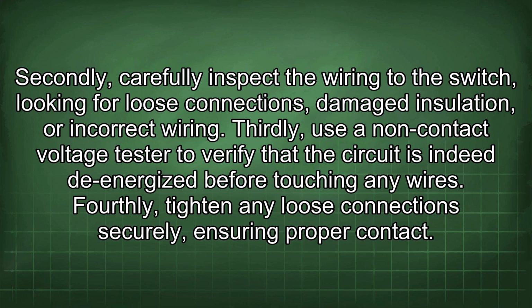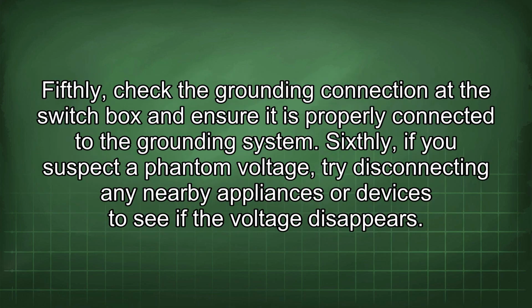Thirdly, use a non-contact voltage tester to verify that the circuit is indeed de-energized before touching any wires. Fourthly, tighten any loose connections securely, ensuring proper contact. Fifthly, check the grounding connection at the switch box and ensure it is properly connected to the grounding system. Sixthly, if you suspect a phantom voltage, try disconnecting any nearby appliances or devices to see if the voltage disappears.